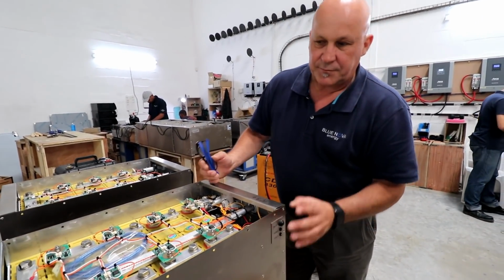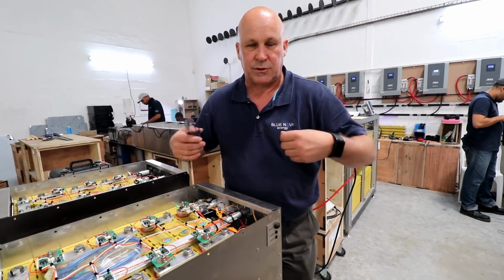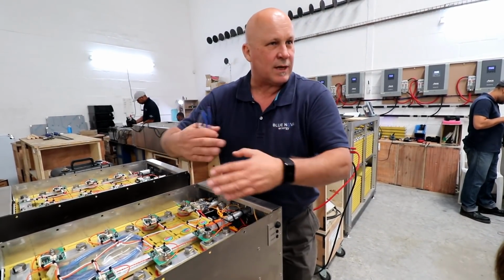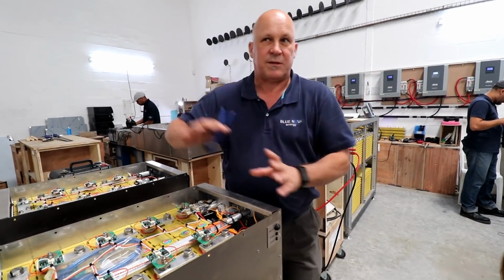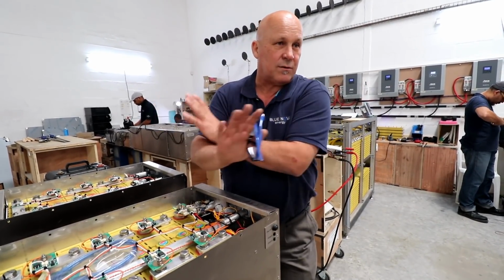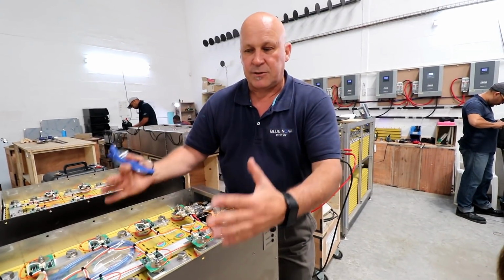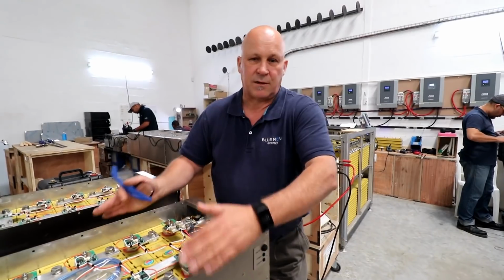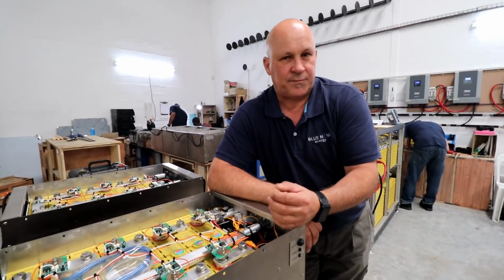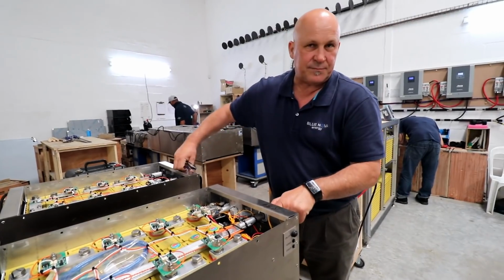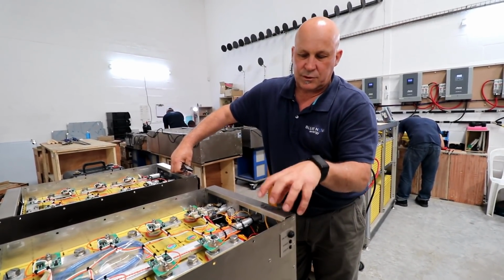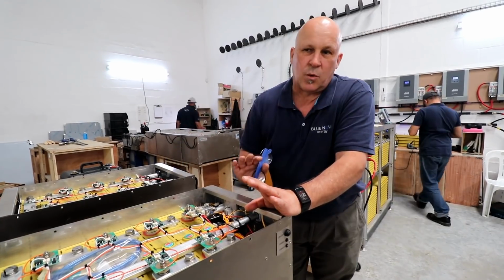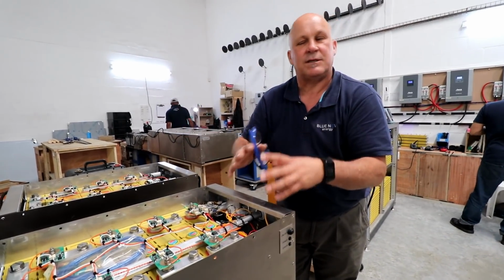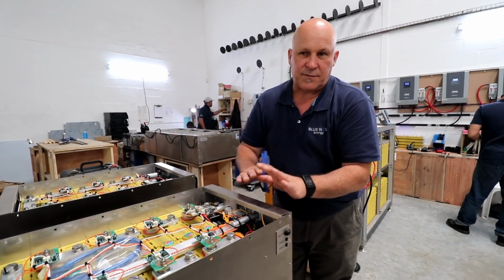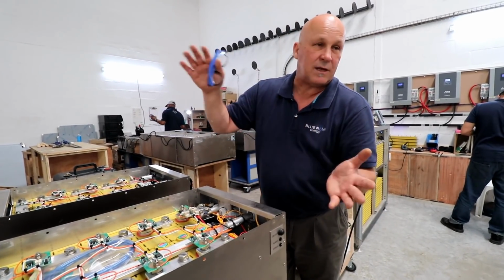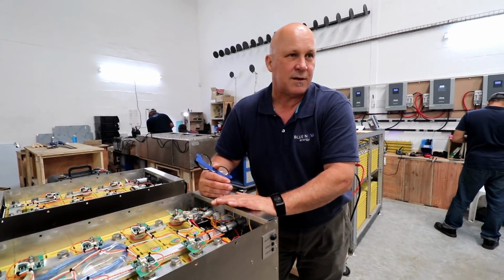Typically when we switch it on, it's also a very dangerous thing switching on a battery because you don't know really what you're connected to. And if there's a short or cables are touching or there's internal fault in the inverter or maybe the chargers have something wrong or somebody shorted them out or connected them incorrectly, these batteries can deliver a huge amount of power. It'll vaporize the equipment. On startup, we monitor the output of the battery. And what we do is we have a little pre-charge circuit inside here, which normally charges up the capacitors inside your inverter or inside your charge controller. And if that voltage doesn't rise to a certain level within a certain period of time, we won't close the breaker. Then we think there's something wrong.